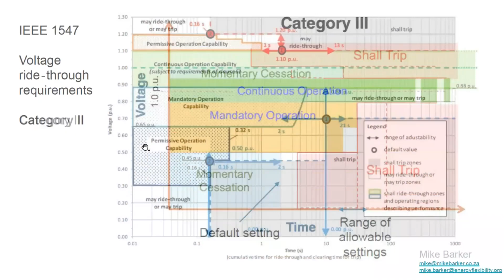You can see anything up to 1.1 per unit, fine, that's great, and anything down to 0.88 PU, that area is great, you can operate there. Then looking at the bottom, we've got the time, and you can see depending on how long these issues last, these dictate how your approach to it, whether you trip, whether you ride through, all of this being adjustable.